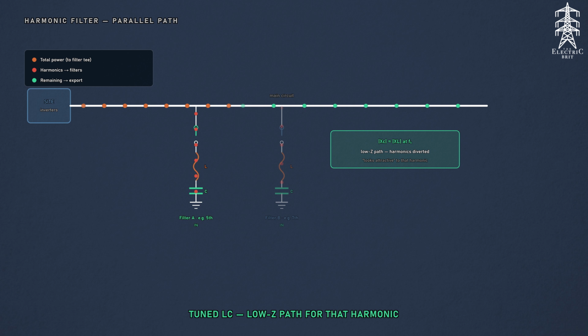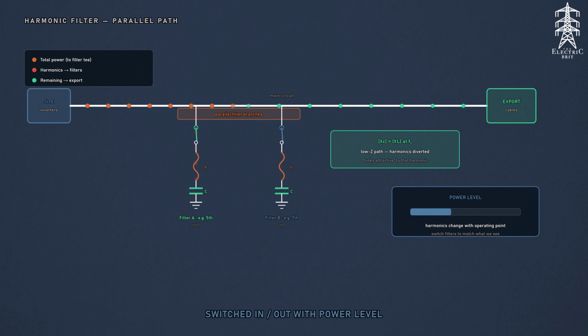Which is why they're in parallel with our main circuit here behind me, and before we get onto the export cables at the end. We can switch them in and out depending on the harmonics we see, which might vary with power level. So if I can make this filter present a very low impedance at 550 Hz, suddenly it looks extremely attractive to our 11th harmonic.